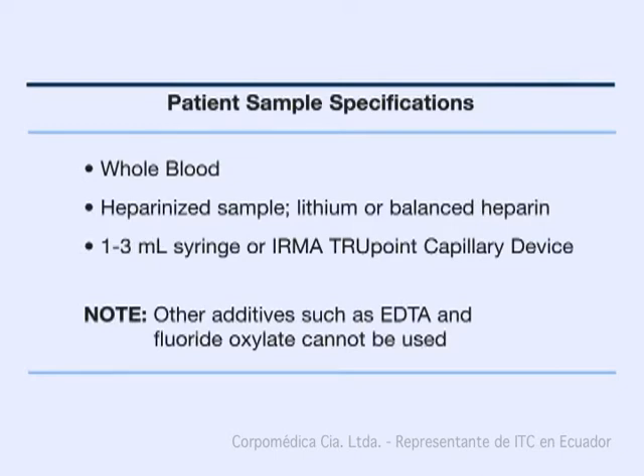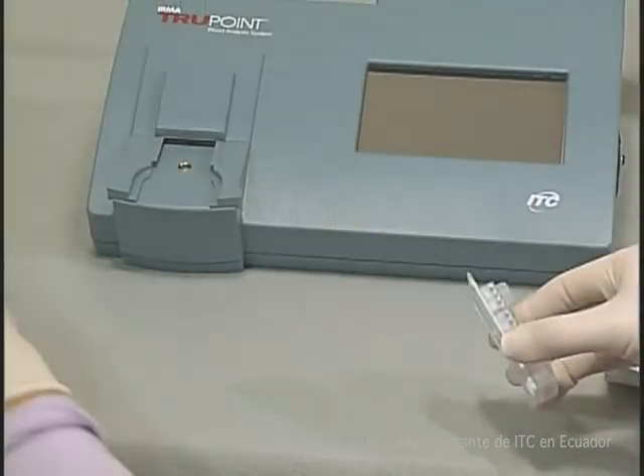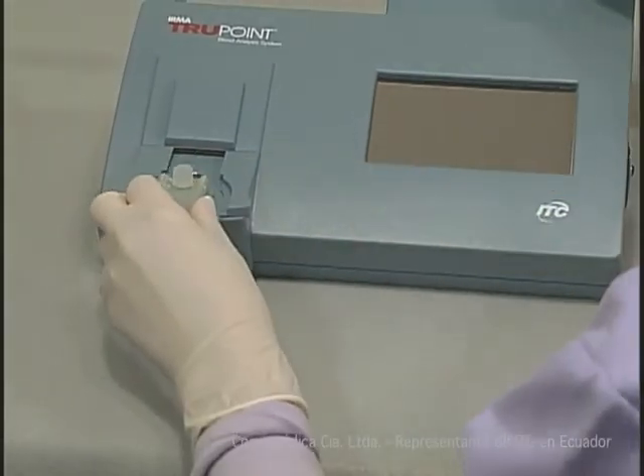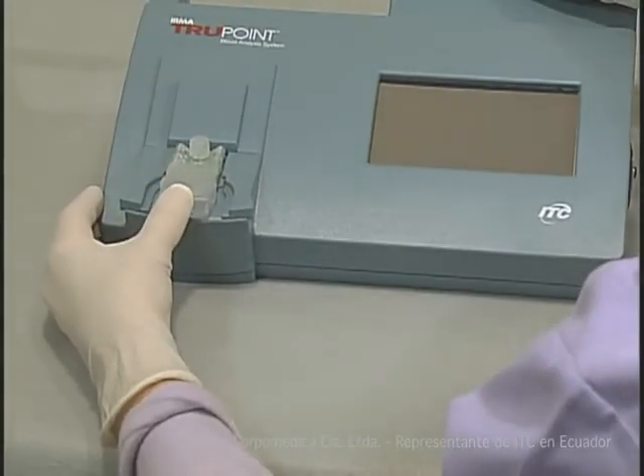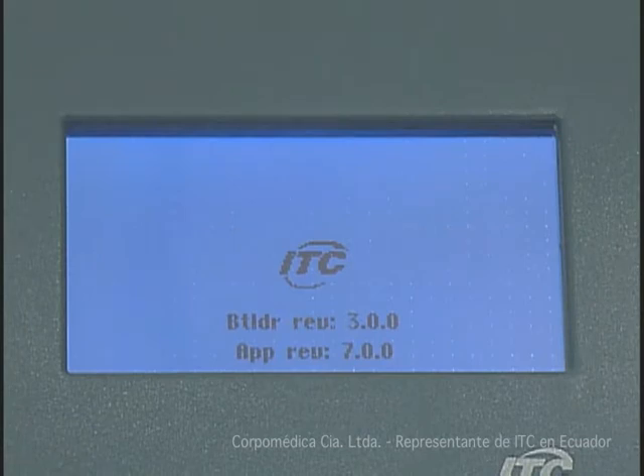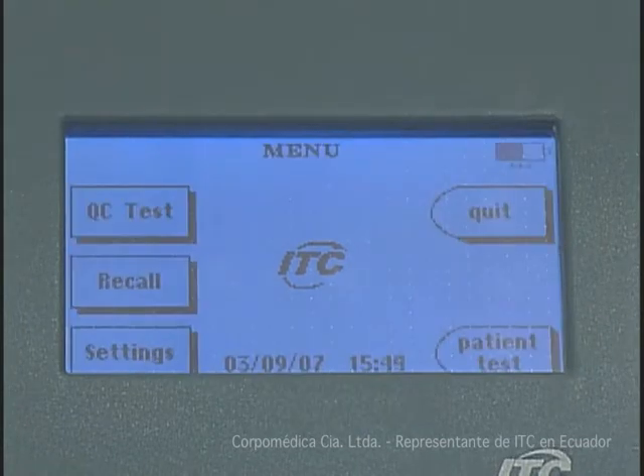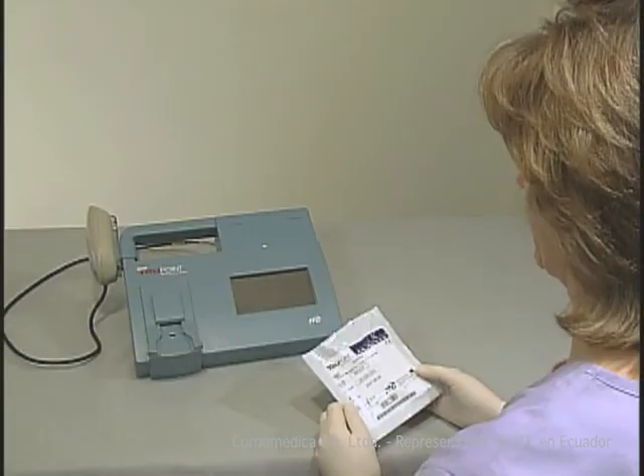Running a patient test is a simple process and can be initiated either by inserting a cartridge into the ITC TruPoint and following screen prompts, or by touching the right edge of the screen to turn the analyzer on and selecting Patient Test from the main menu. Let's initiate a patient test by inserting the cartridge.